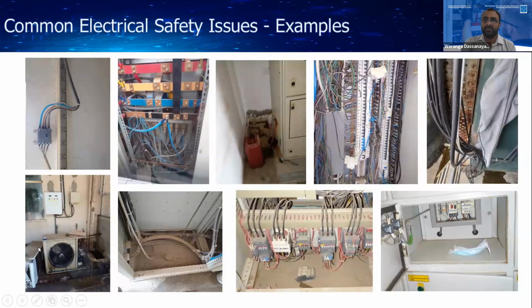In this picture, you can see there is no access for this distribution board. Under this distribution board, an outdoor AC unit has been placed. So in an emergency situation, no one can access this power distribution board and switch off, or the maintenance cannot be done easily. The maintenance person should climb up on the outdoor AC unit to switch off the power distribution board or to do the maintenance.